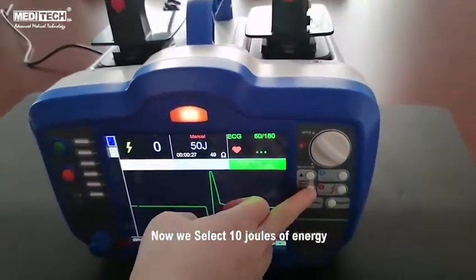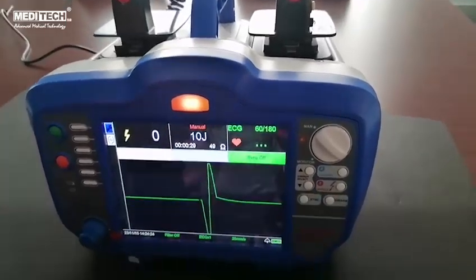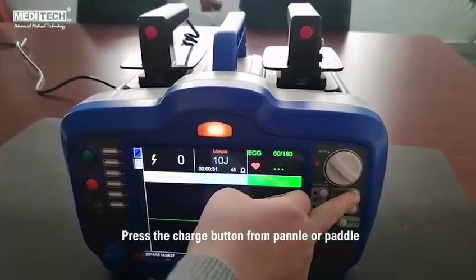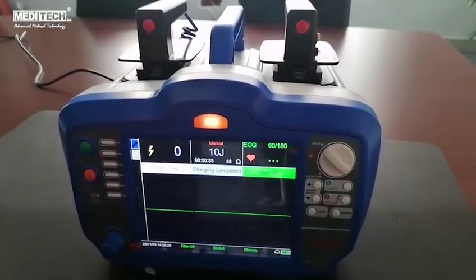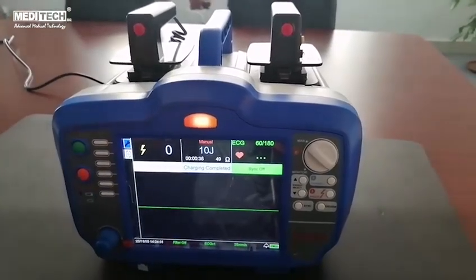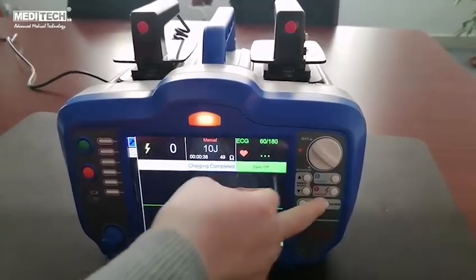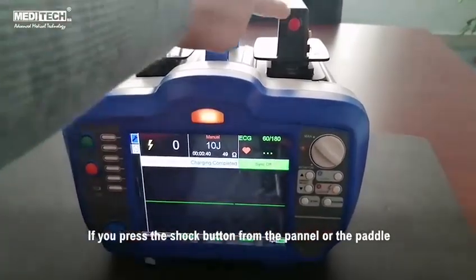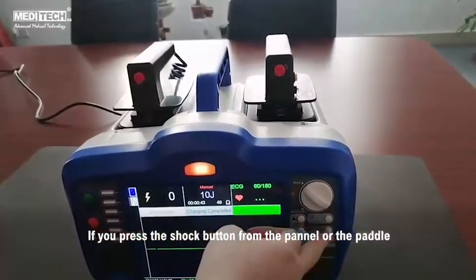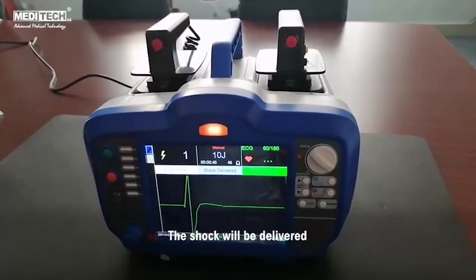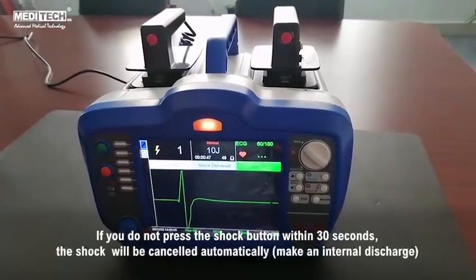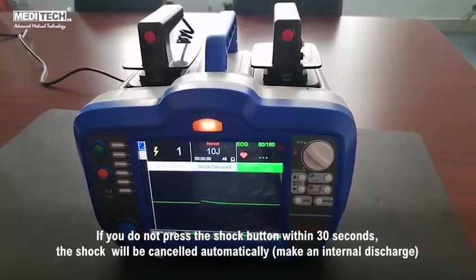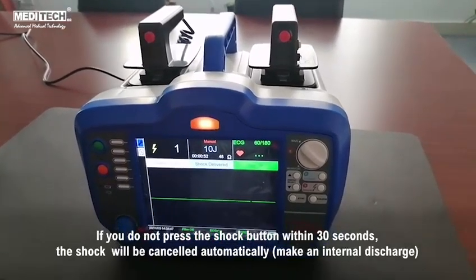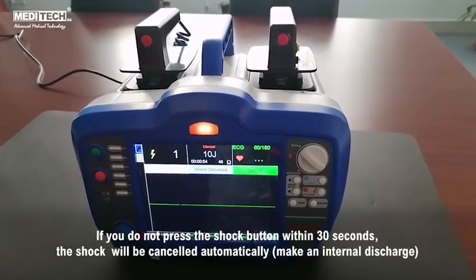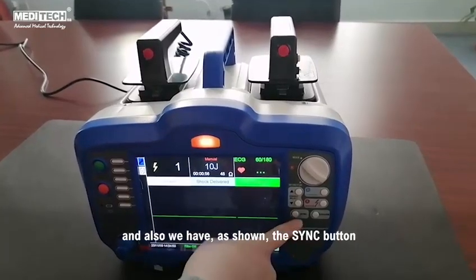Now we select 10 joules of energy. Press the charge button from the panel or paddle. If you press the shock button from the panel or the paddle, the shock will be delivered. If you do not press the shock button within 30 seconds, the shock will be cancelled automatically. Make an internal discharge. And also, we have, as shown, the SYNC button.